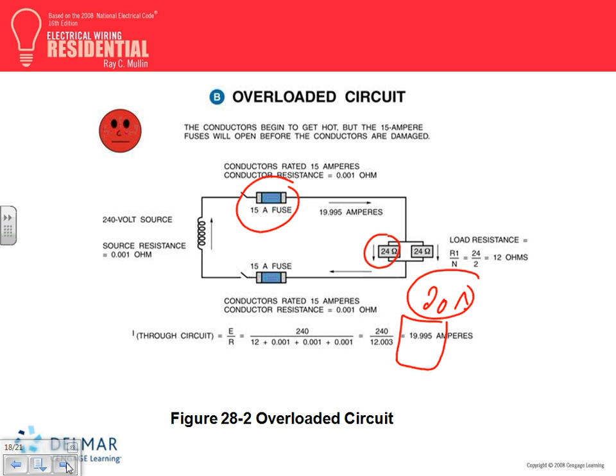So what's going to happen? In a case like this, Brad, you'll be surprised. You can run like this for almost an hour on a fuse or circuit breaker until it heats the fuse hard enough to open. And the conductors can handle that overload. Number 14 conductor here, you guys remember number 14? Number 14 is rated for 20 amps. We don't load it to 20 amps, but it's rated for 20 amps. So the fuse will open within probably half an hour to an hour.